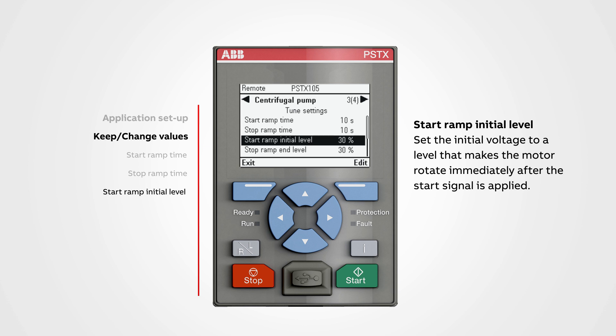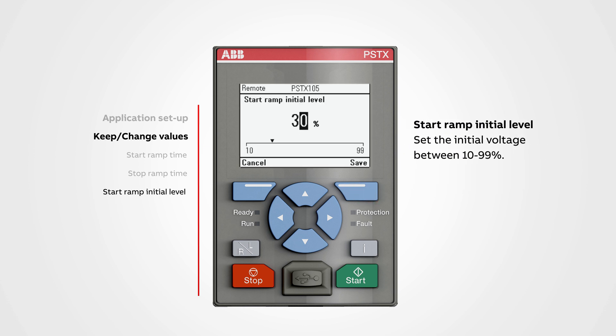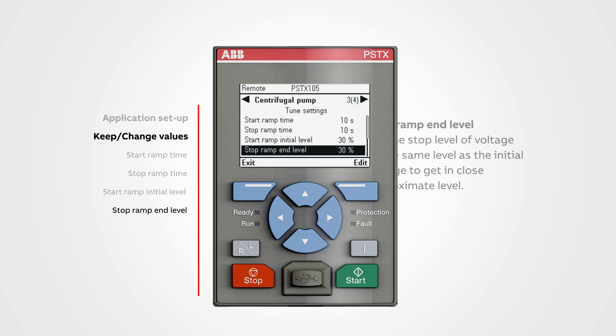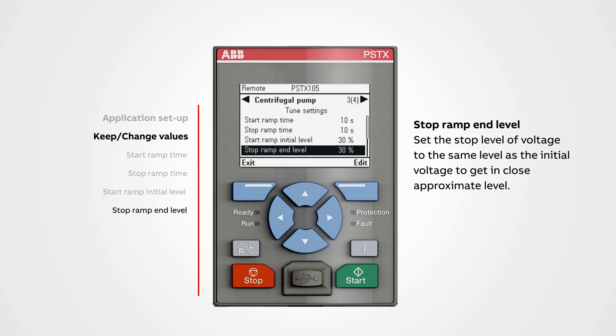Start ramp initial level sets the initial voltage to a level that makes the motor rotate immediately after the start signal is applied. If the initial voltage is too low, the engine will stall initially and generate excessive heat. If the level is too high, the motor will start with a jerk. To change a value, push edit. We can set the initial voltage between 10 to 99 percent. Use the navigation buttons to change the value, then push save.